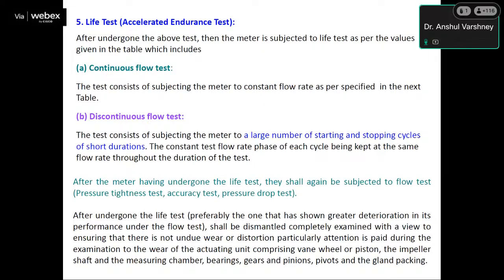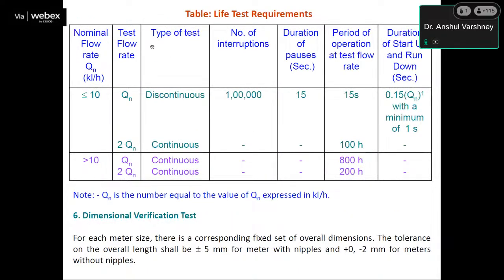Life test. After undergoing the above tests, the meter is subjected to the life test as per the values given in the standard. Basically, the continuous flow test consists of subjecting the meter to a constant flow rate as specified in the table, and then the discontinuous flow test. For the discontinuous test, the number of interruptions should be 1 lakh at a nominal flow rate of 10 kiloliter per hour, and for continuous operation it is more than 10. The period of operation is 800 hours, and 200 hours for continuous operation at nominal flow and double of nominal.